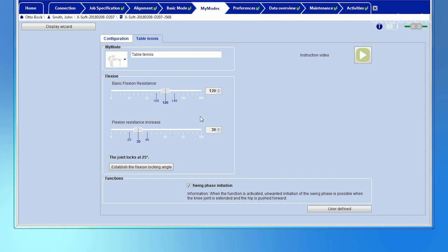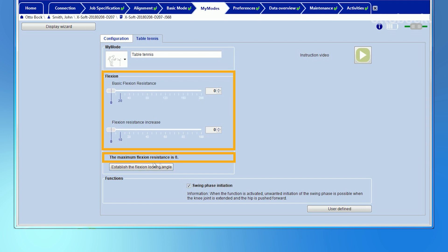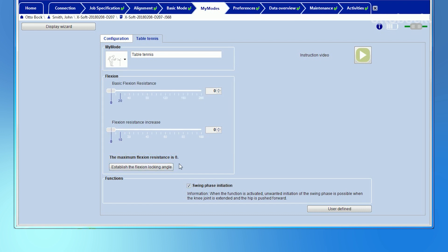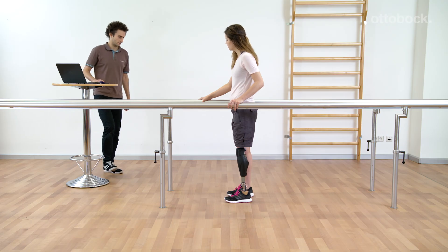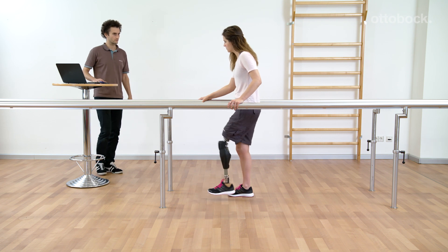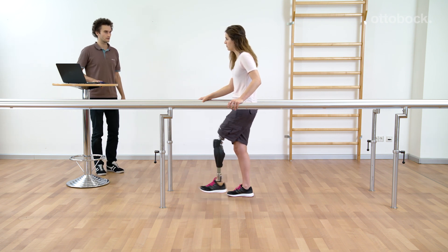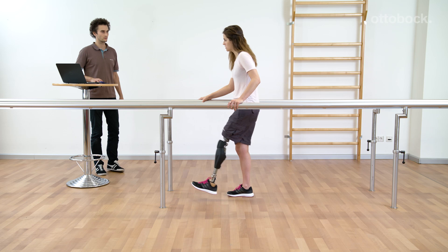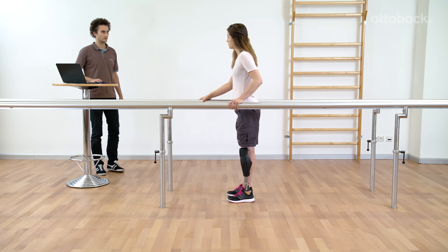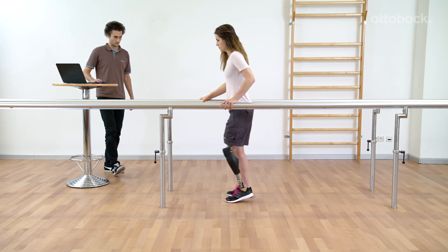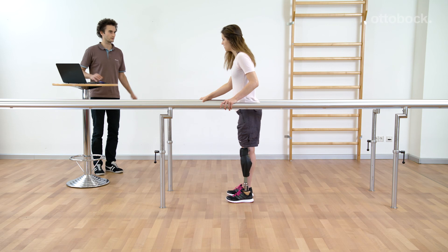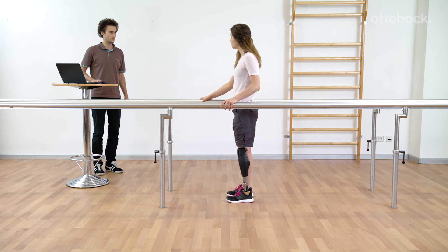The knee joint can flex easier and the flexion movement is stopped a little more abruptly at the target angle. If both parameters for the flexion behavior are set at their lowest level, the values are the same as in cycling mode. The knee joint is free swinging and there is no increase in the resistance. The user will need to stand securely during this state. If the user wants to perform some steps, the knee joint has to be controlled by active hip extension to prevent collapse of the knee.